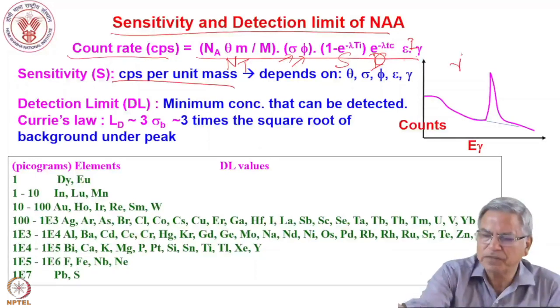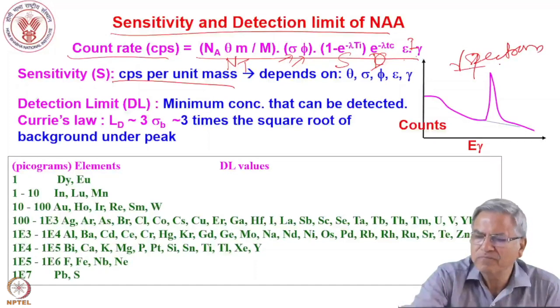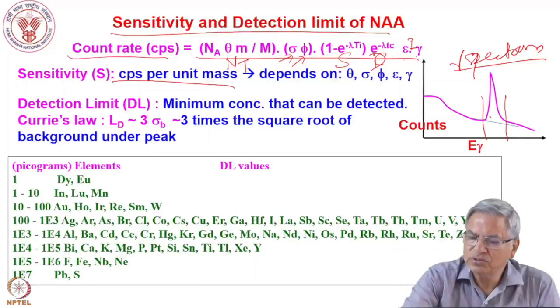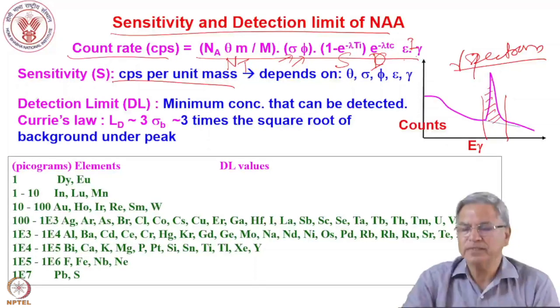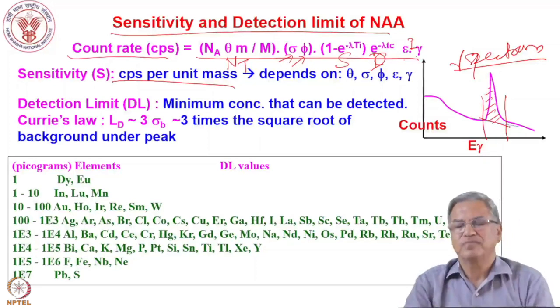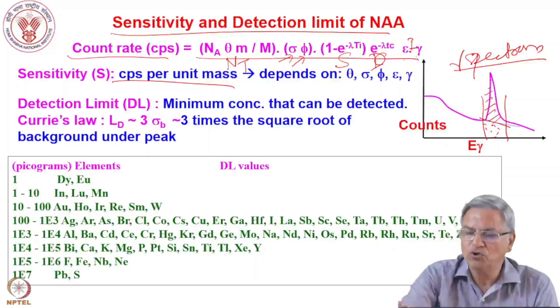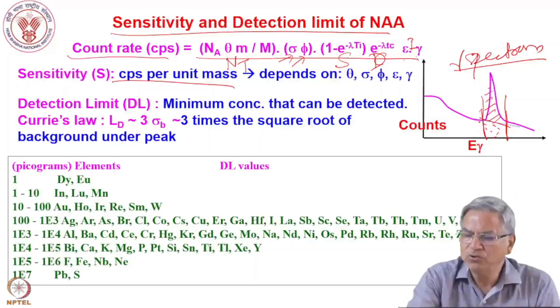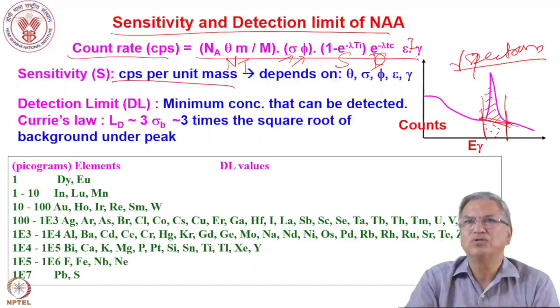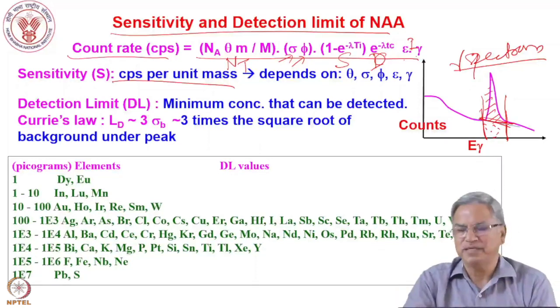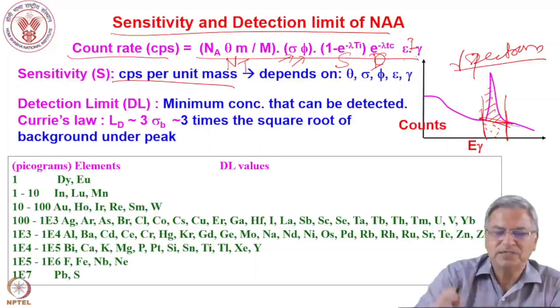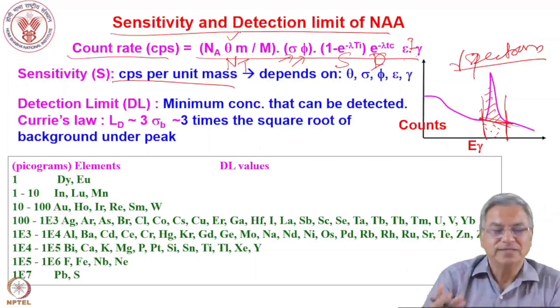The second quantity is the detection limit — the minimum quantity that can be determined by this technique. When there is no sample, you get a flat background in the gamma spectrum, sometimes with a small bump that could be confused with a real signal. What is done to define the detection limit is based on Currie's law: if you record the background gamma ray spectrum in the region of the peak of interest, the standard deviation of background counts σ_b equals the square root of the background counts B, because radiation counting follows a Poisson distribution where variance equals the mean.